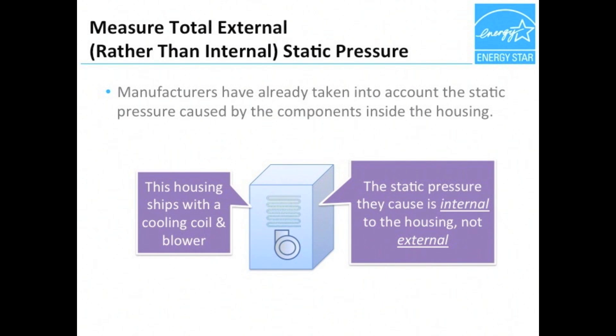Keep in mind that to measure the external static pressure, you'll need to select one hole before and one hole after the components the manufacturer considers internal to the equipment. For example, the manufacturer has likely already accounted for the static pressure changes caused by the fan housing and the fan itself. It's also possible that the manufacturer has accounted for static pressure changes caused by other components that ship in the same housing as the fan, such as the cooling coil or a factory installed filter, while others might not.